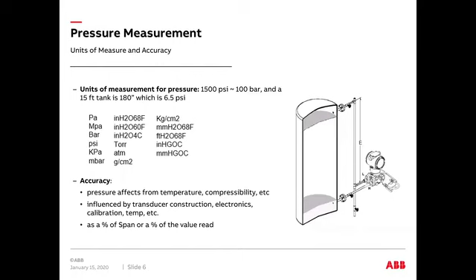Here's one example of an accuracy example. ABB produces a multivariable, the 266JST. If you look at an Emerson one or a Foxboro one, you may see percentage of span or percentage of the value. Sometimes it's a mix. On the ABB, you have plus or minus 0.04% of the value, and that's up to a 20-to-1 turn down. So if you have a 1,000 inch transmitter and you're turning that down to smaller readings, you're still going to have that type of accuracy.